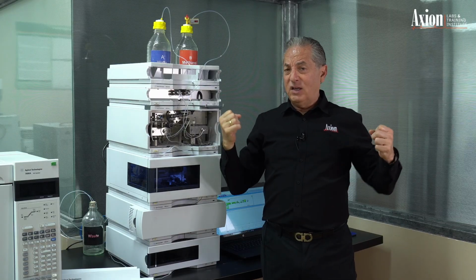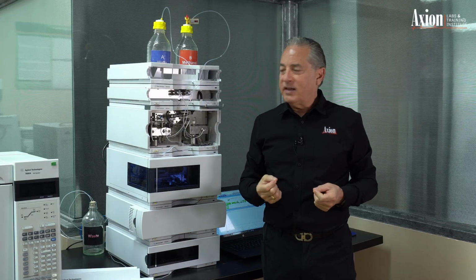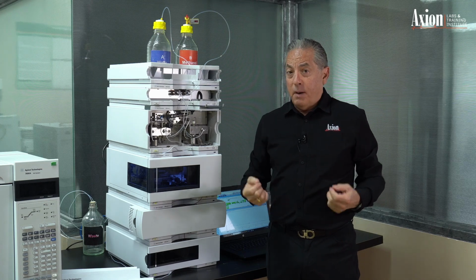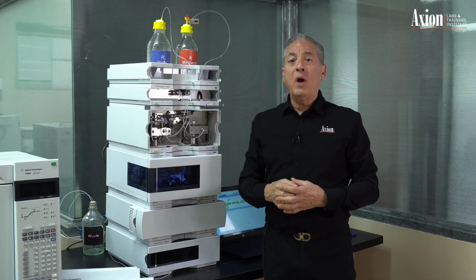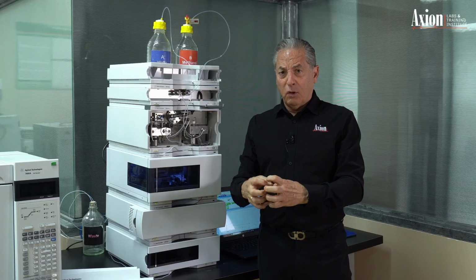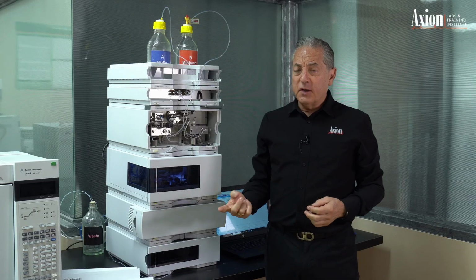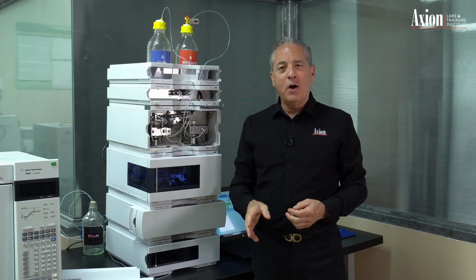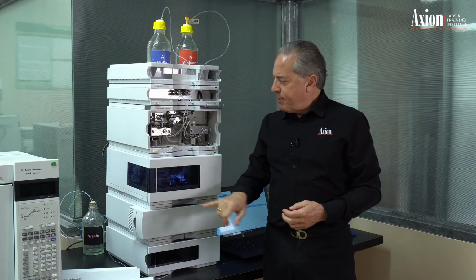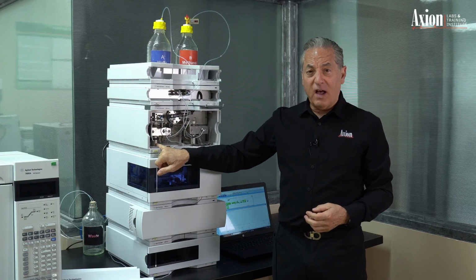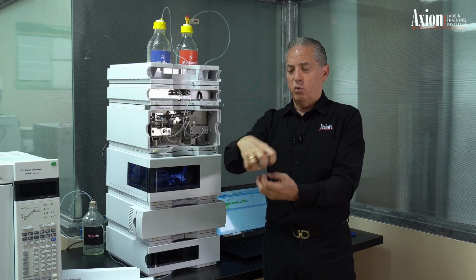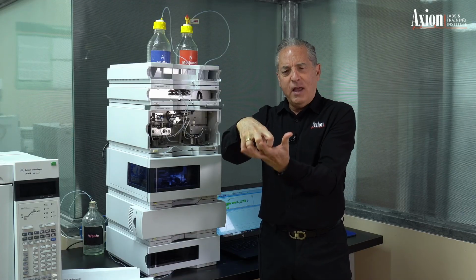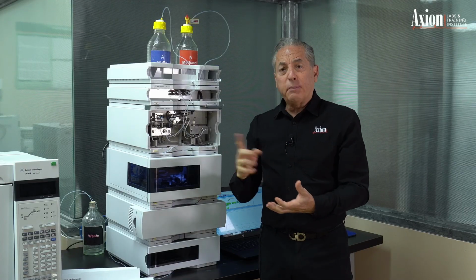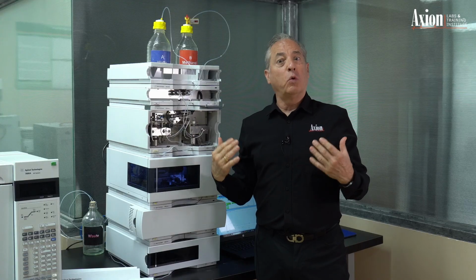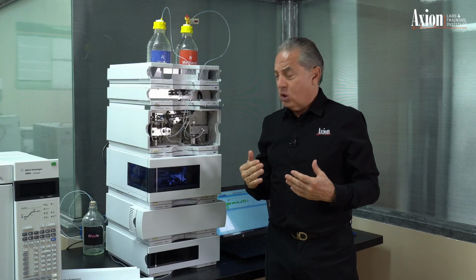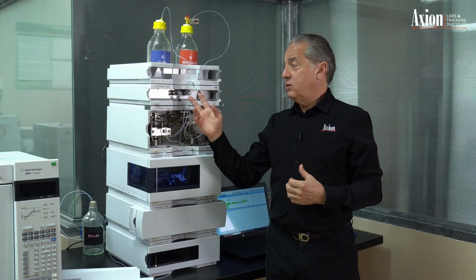We have now freshly degassed mobile phase. There's no dissolved gases. So now when we draw them into the pump, we don't have to worry about bubble formation. Number one cause of problems in HPLC, hands down, is an air bubble in the pump. An air bubble gets caught in the inlet check valve, and there's a little ruby sphere in there, and it floats it high. When that happens, we get pressure fluctuations, and the pump just doesn't work the way it's supposed to be working. So we want to avoid that by using the degassers.